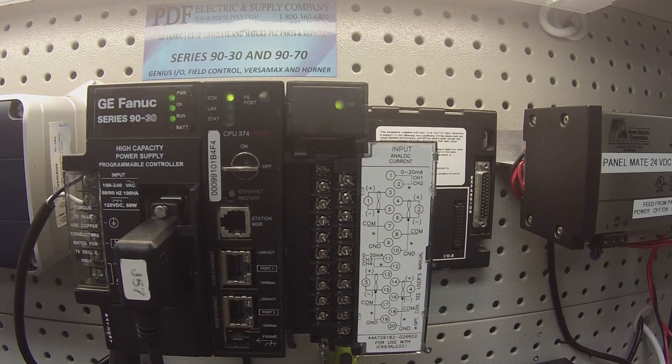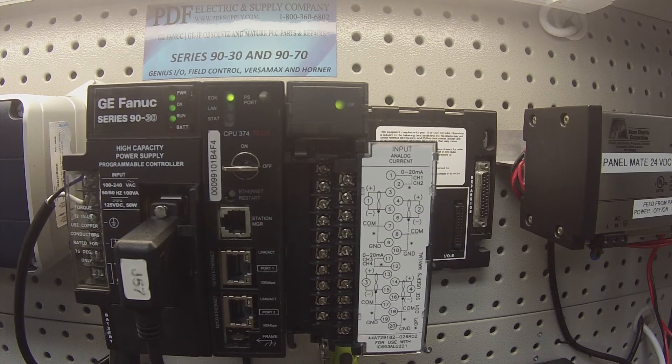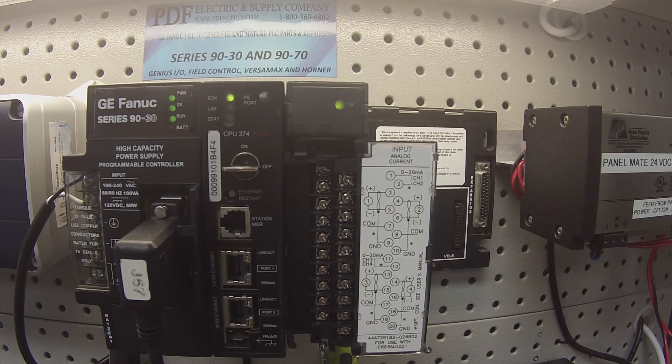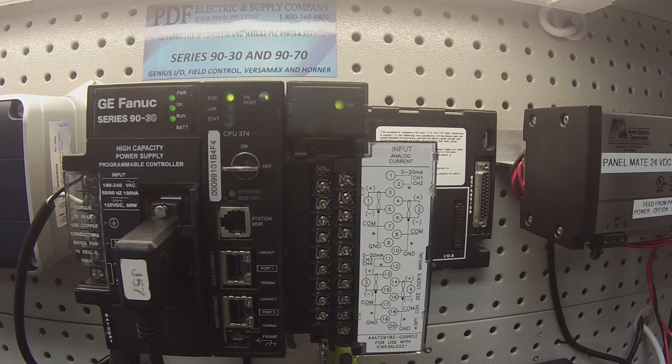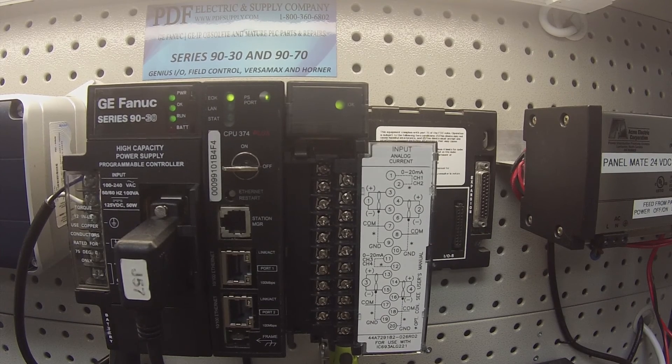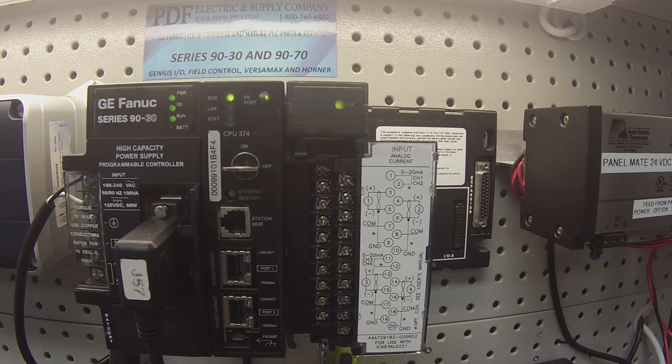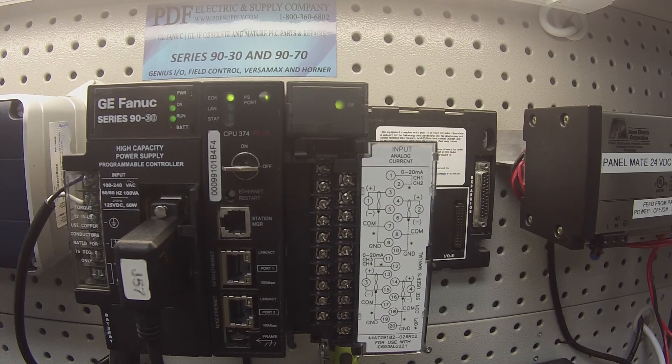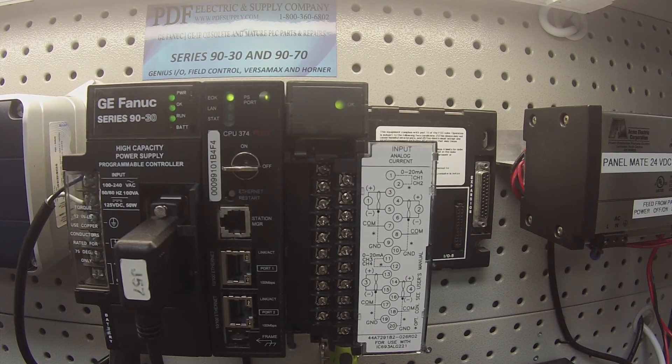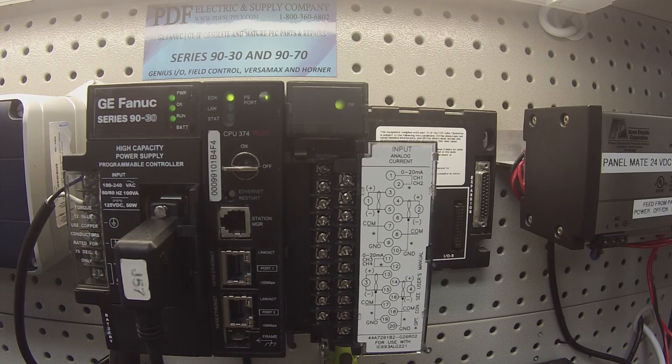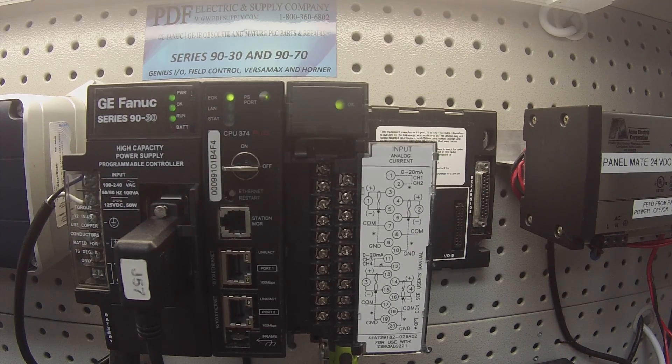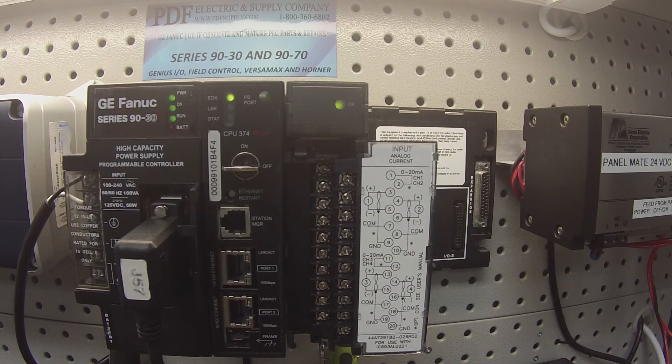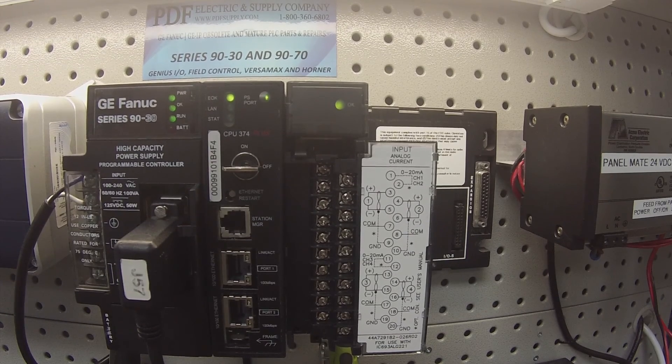Occasionally when one of these cards is bad, it'll give you a reading, but it'll automatically give you the full reading of 32,000. In other words, you would put the probe on at any milliamp value and it would give you full value. So it's an erroneous reading. This is a typical problem with analog current modules and it's something we repair here at PDF Supply.